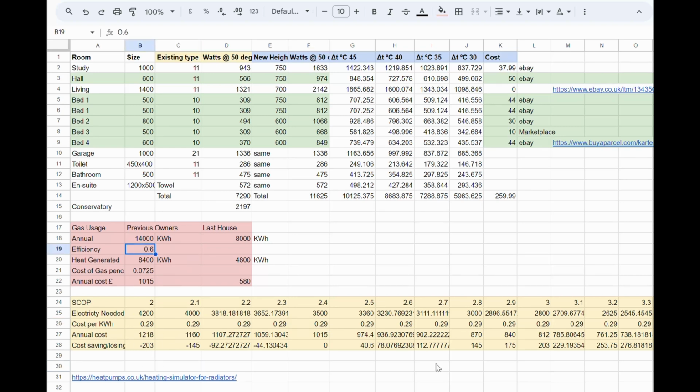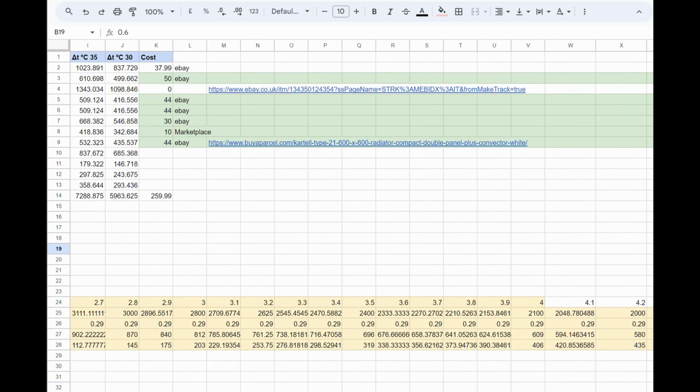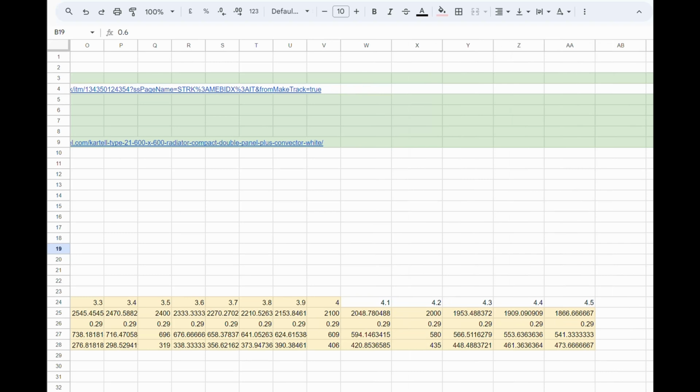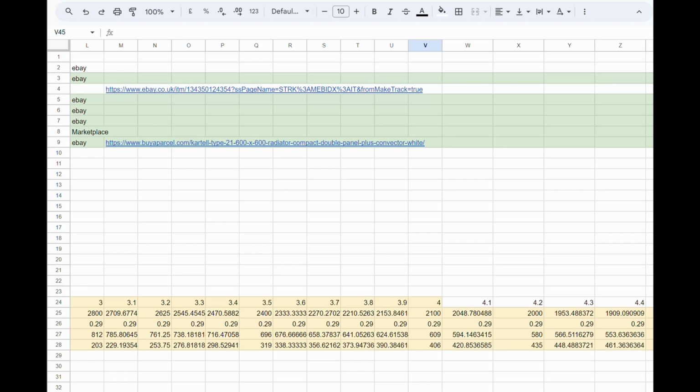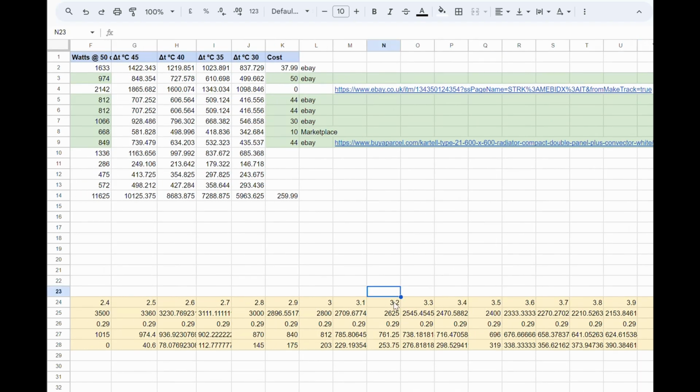Where do we want to go next? This brings me on to how our heat pump is performing at the moment. Our heating, the last time I checked, was performing at a COP of 4.3, which would save us £448 in a year. But the hot water side of it was performing at a COP of 3.2. So on the hot water side, which is typically about 25% of our consumption, is a saving of £253.